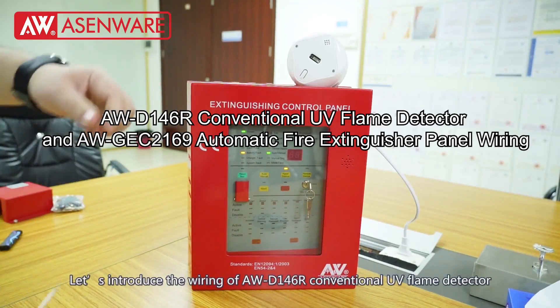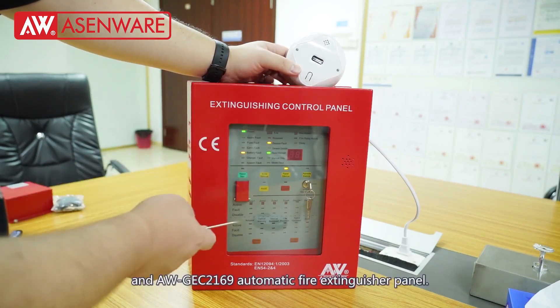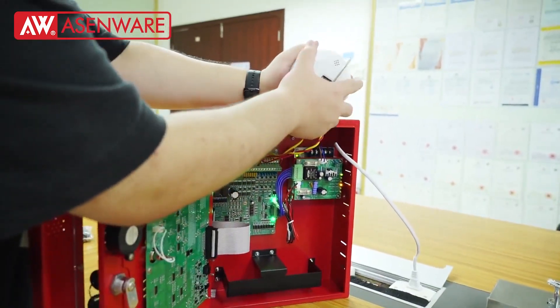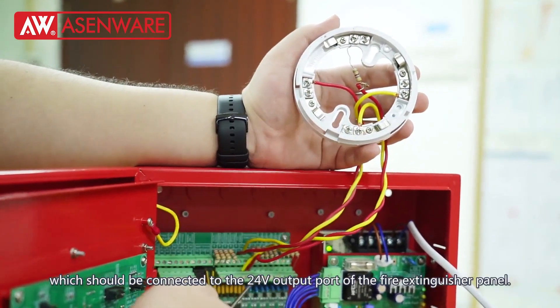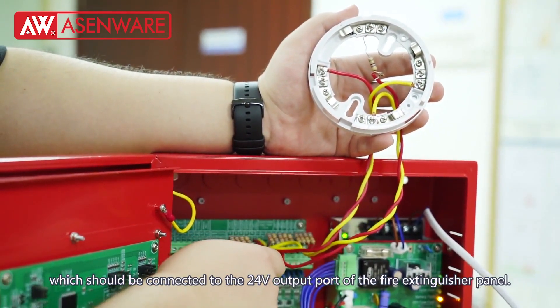Let's introduce the wiring of AWD146R Conventional UV Flame Detector and AW-GEC2169 Automatic Fire Extinguisher Panel. The power pins of the UV flame detector base are terminals 2 and 5, which should be connected to the 24V output port of the fire extinguisher panel.